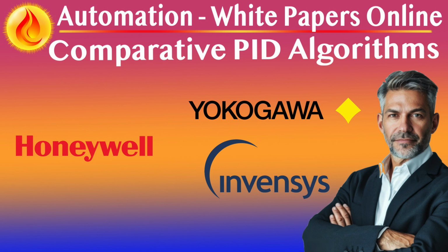Honeywell ensures safe and stable D action by design, while Invensys places more burden on the engineer to manage D-term behavior. This makes Honeywell better for derivative-heavy loops or fast response systems where actuator life and noise suppression are critical.